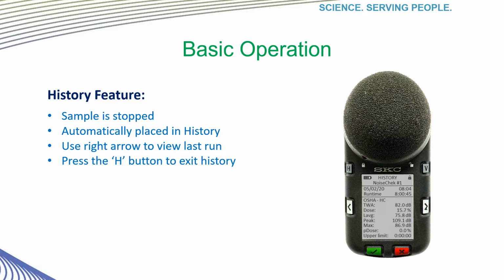After the sample has stopped, you will immediately be defaulted to the device history, where you will see the complete summary of the last run. If you want to review the data from this session, simply use the right arrow to scroll through the data. Keep in mind you will be able to see all the summary data for all internal dosimeters you have set up in the unit, not just one screen of summary. When you're done viewing this information, pressing the H button will exit the history screen and return to the startup screen.